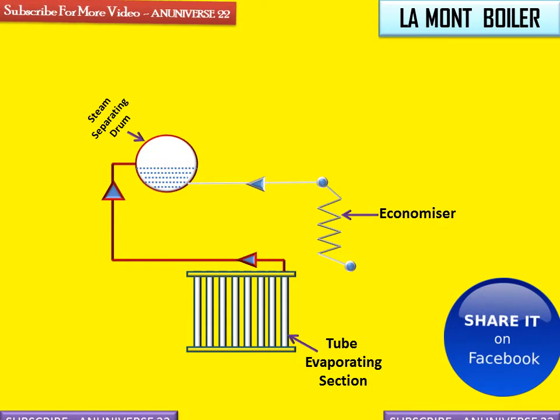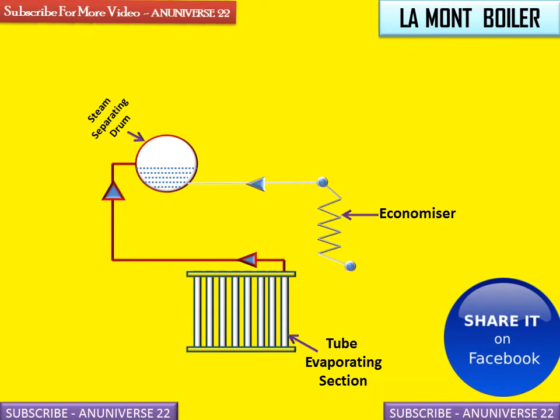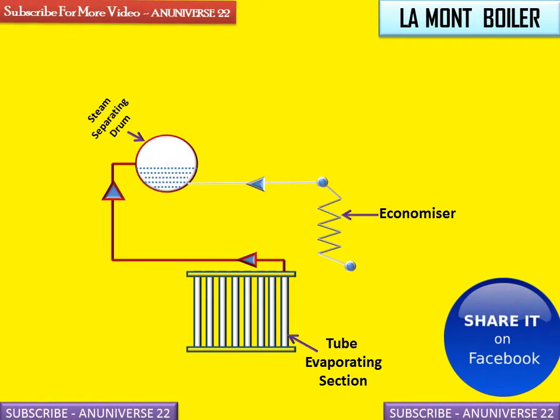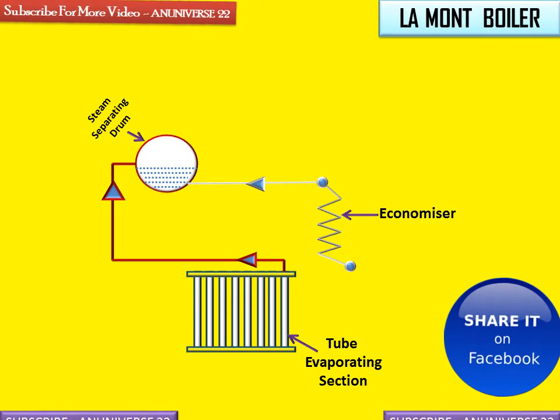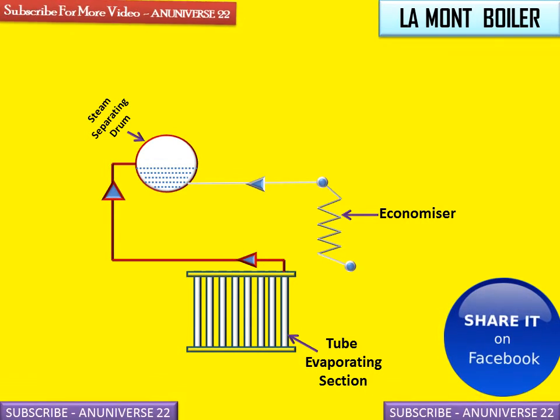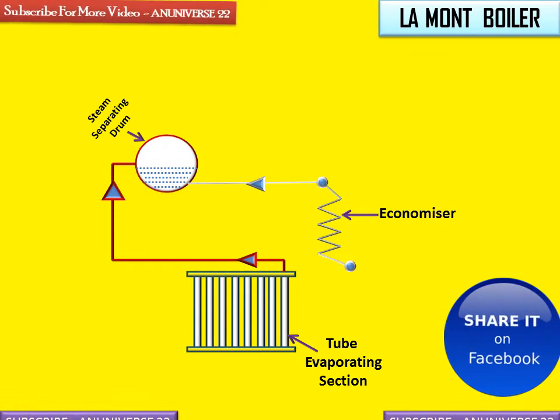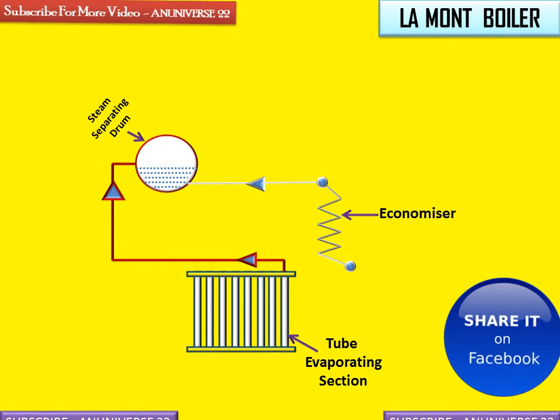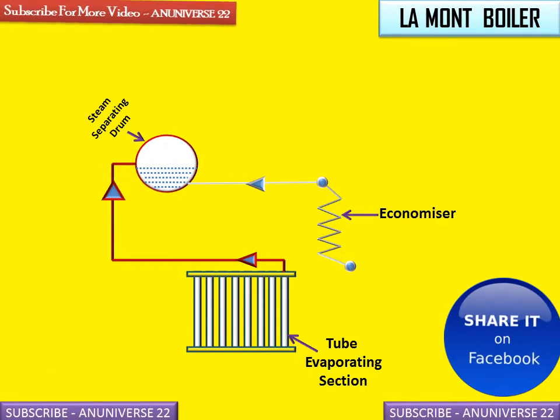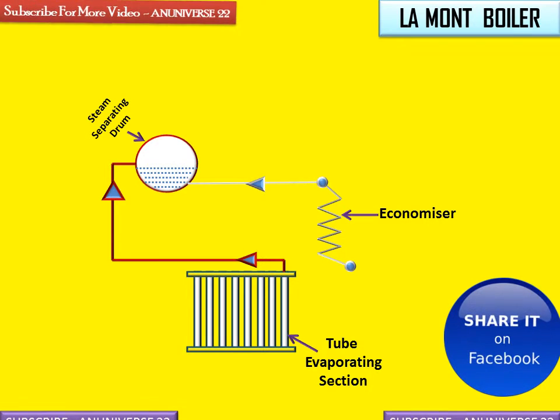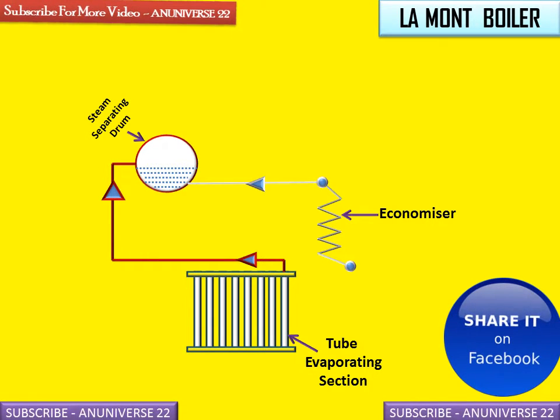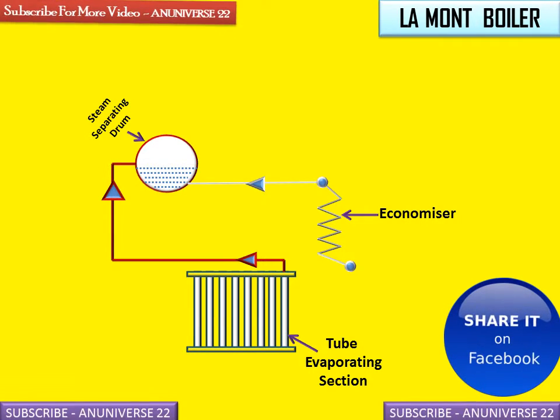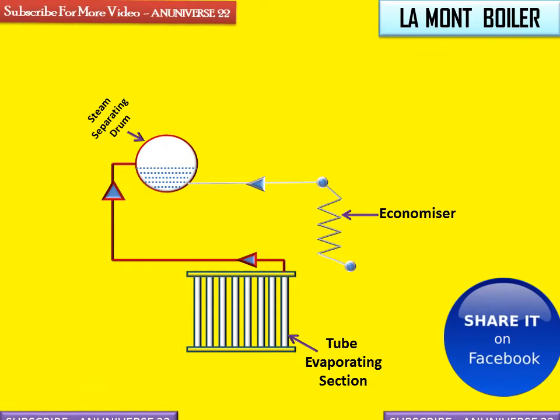This is the steam separating drum. The steam separator is situated outside the boiler. The mixture of water and steam from the evaporator tube is sent to the steam separator, where it separates the steam and sends it to the super heater. The remaining water is sent back to the economizer.